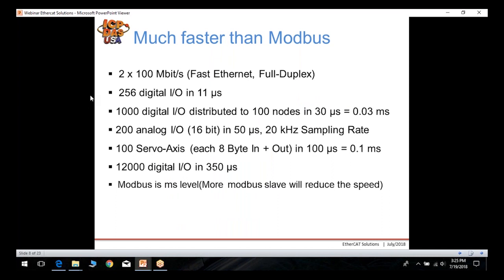EtherCAT is much faster than Modbus. It communicates via Ethernet and is full duplex communication. You can have up to 256 digital I/O processed in 11 microseconds, and 1,000 digital I/O distributed to 100 nodes in just 30 microseconds.